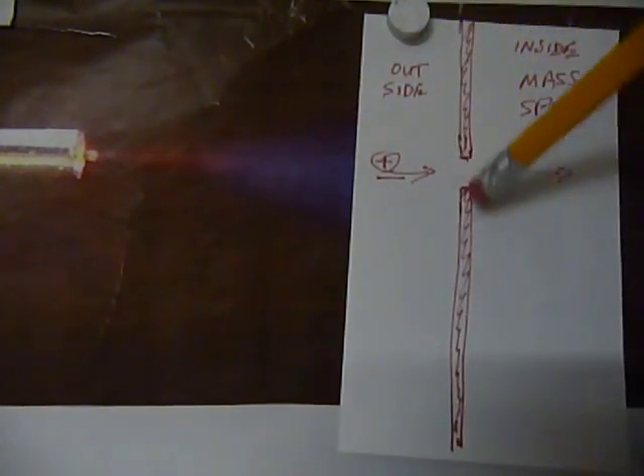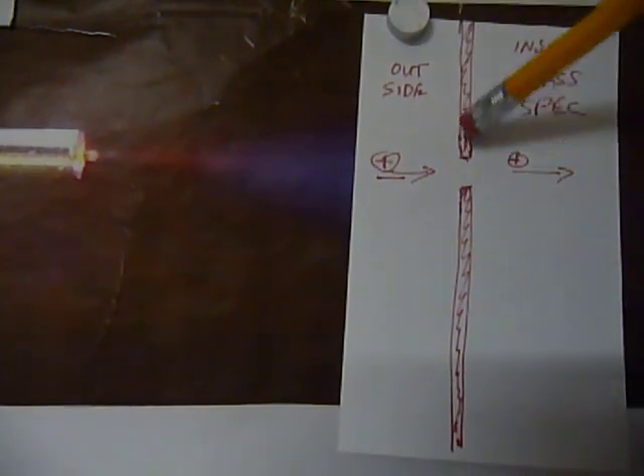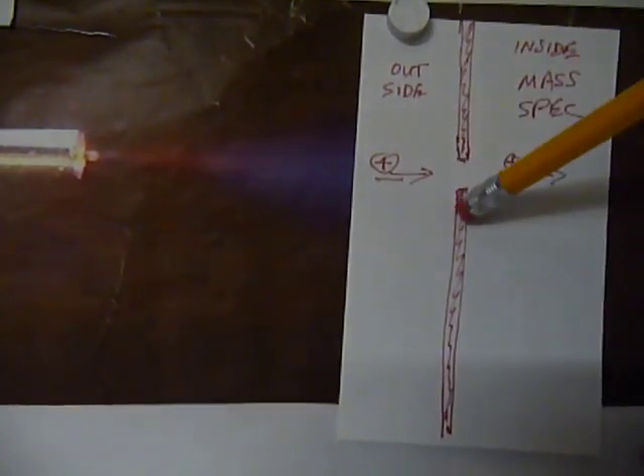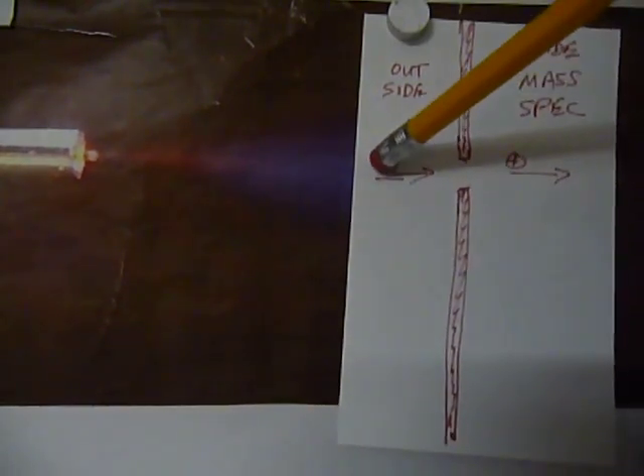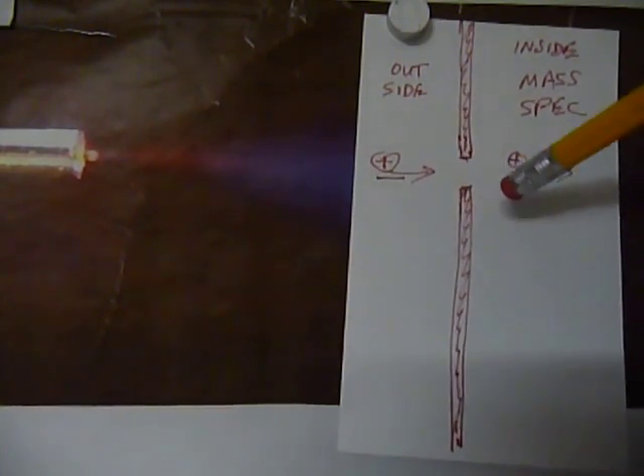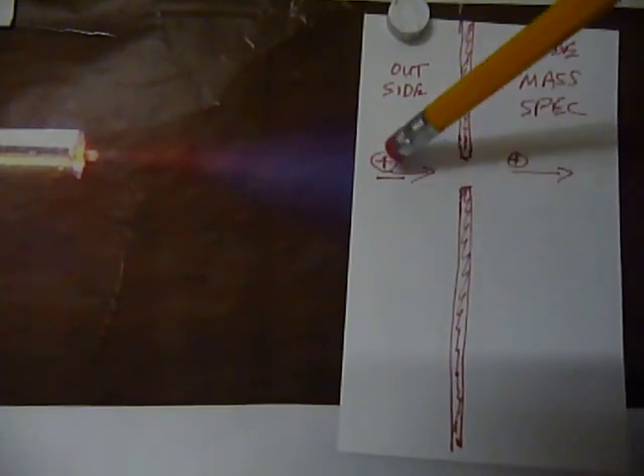And then, typically, there's an opening into the mass spec. That opening has to have some sort of a charge in order to prevent the ions from grounding out and losing their charge as they're making their way into the mass spec.